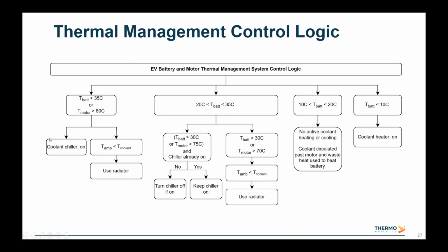We implemented thermal control logic to decide which operations to use and when, shown here, based on chosen thresholds for the battery and motor temperatures. When the battery and motor temperatures are very hot, we turn on the chiller to cool the coolant in most cases. At moderate temperatures, we make decisions based on these criteria shown here.